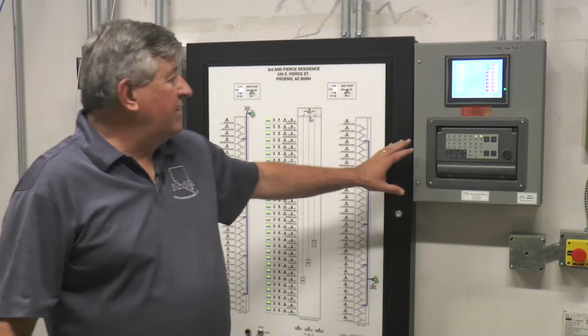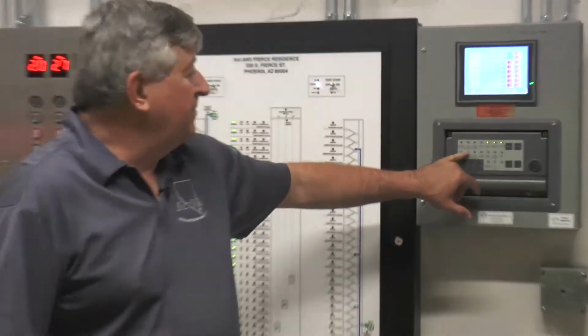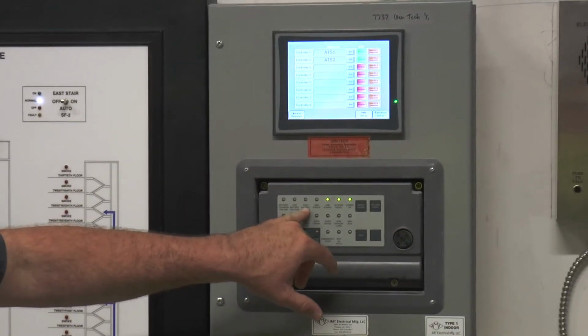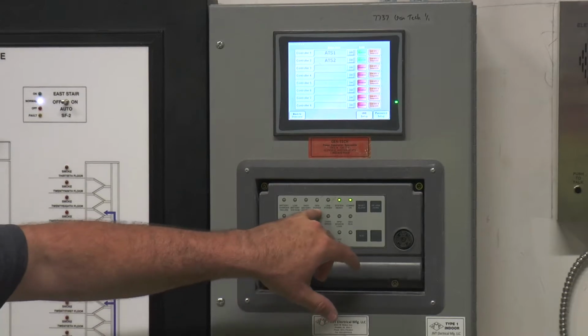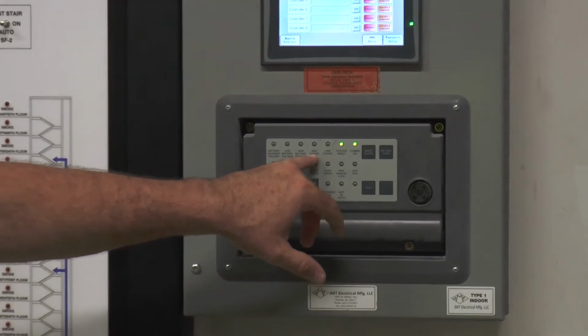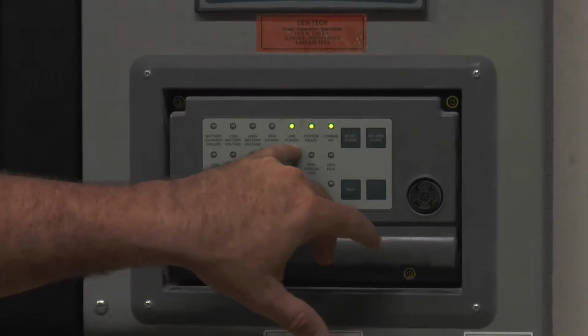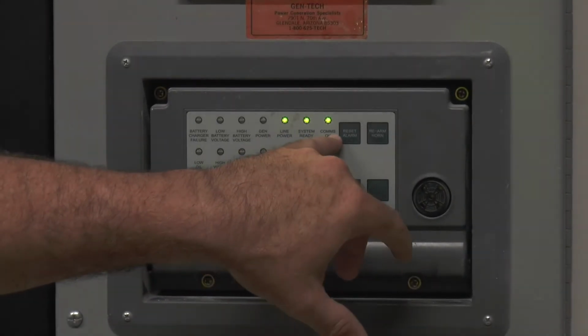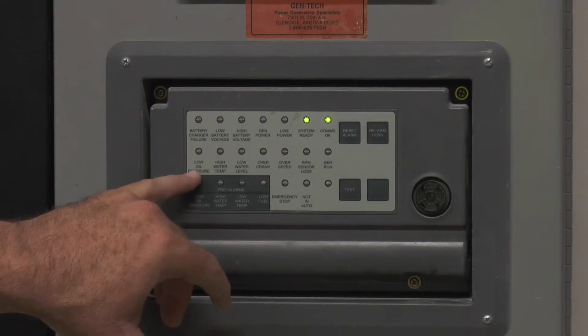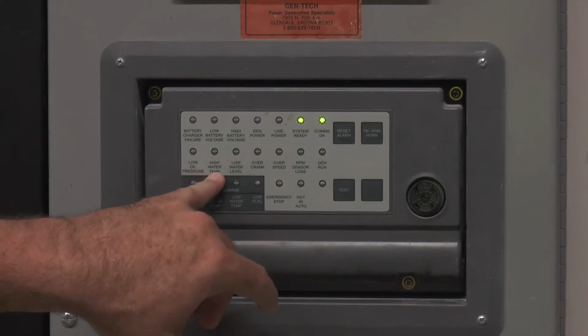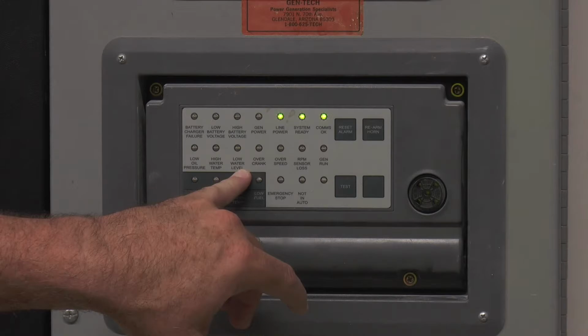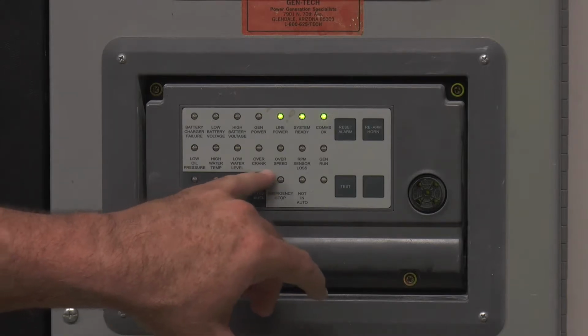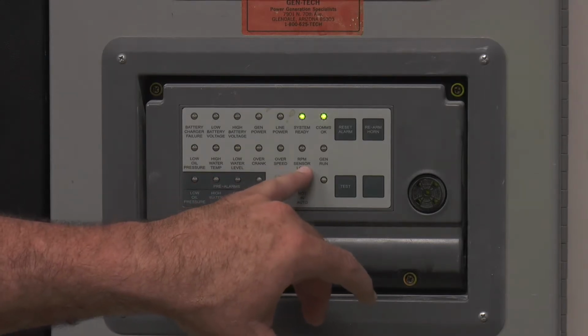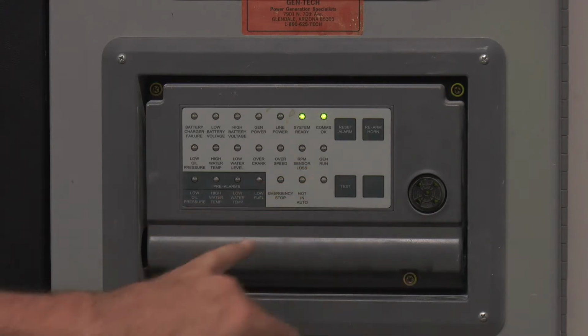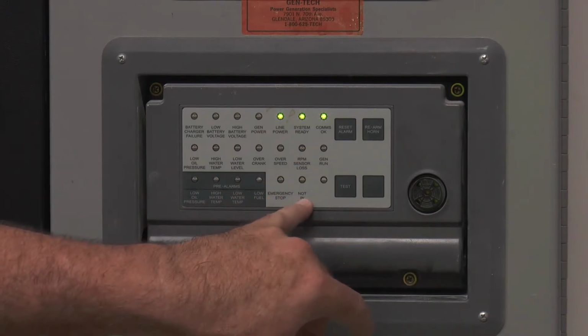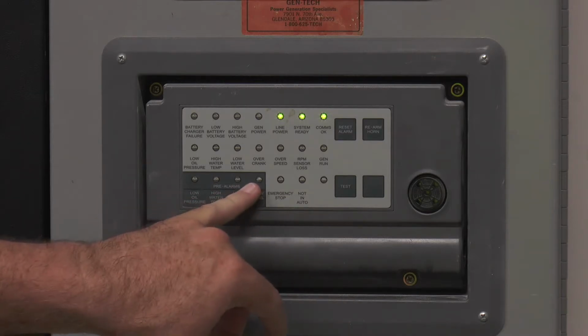The alarms are set for battery charger failure, low battery voltage, and high battery voltage. You're going to have gen power, so anytime the generator is running, this indication light will be on. Line power, system ready, and comms talking. You will also have a low oil pressure shutdown, high water temp shutdown, low water level shutdown, overcrank, overspeed, loss of RPM, and generator running. And then you've got an e-stop and not in auto. And then you have all your pre-alarms over here.